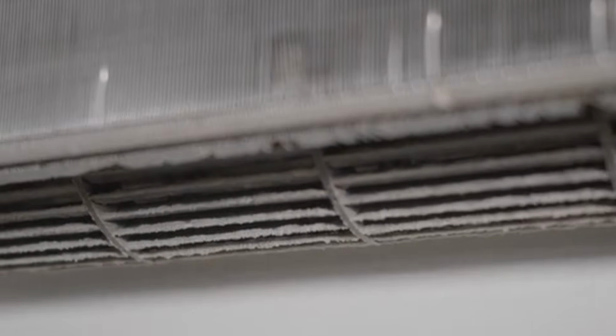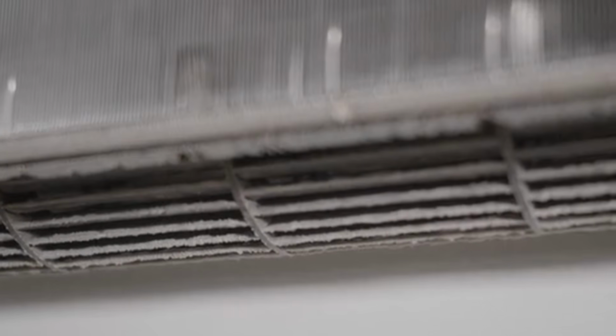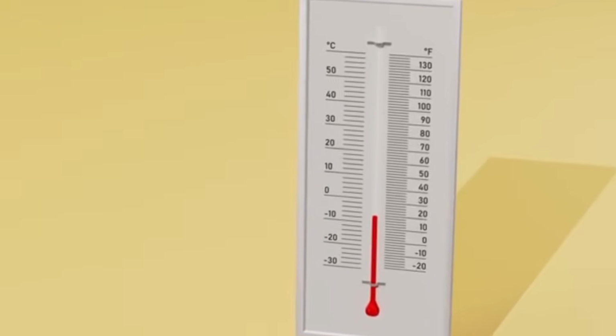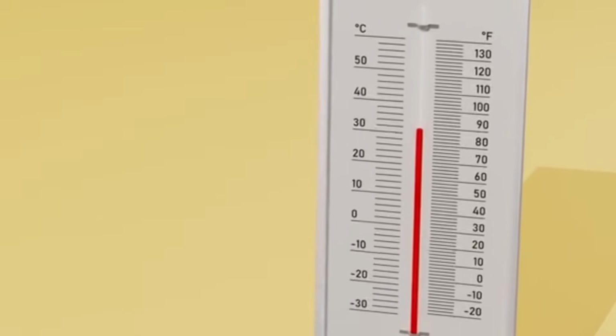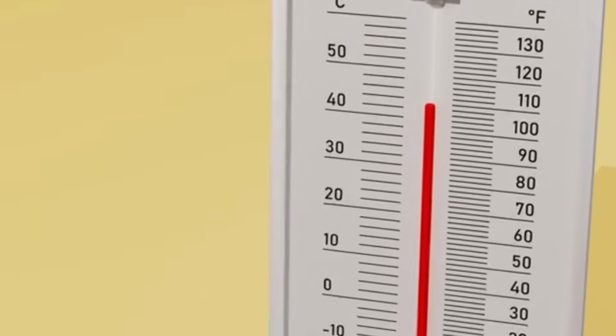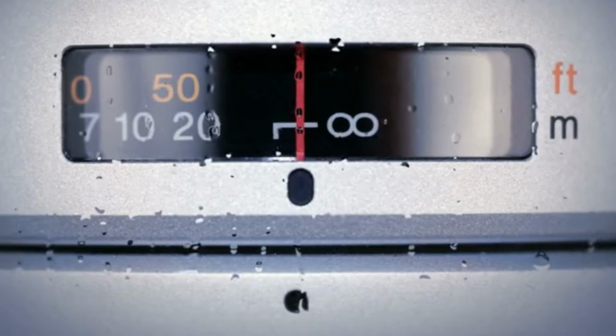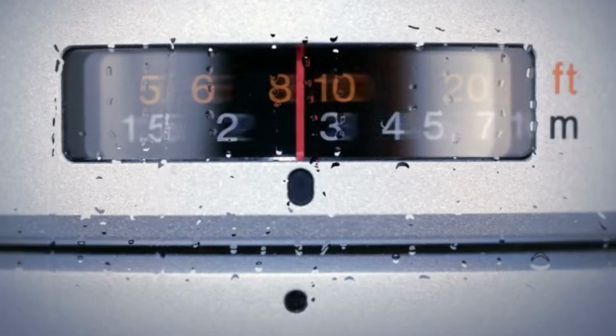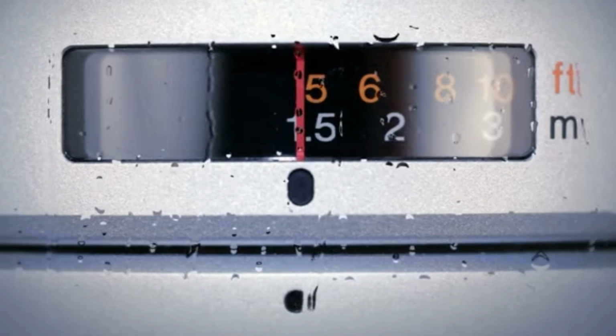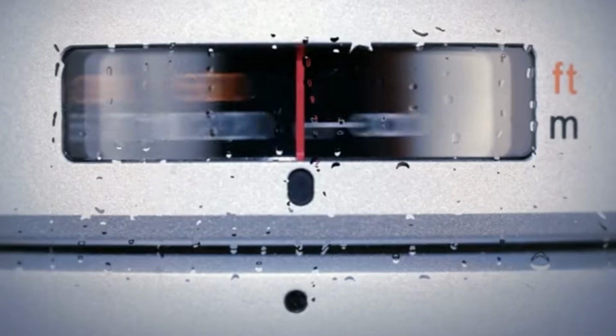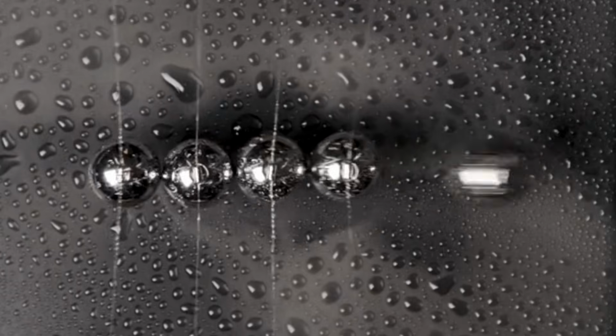However, and this is the part that most people miss, the radiator core, where the cold water meets the indoor air, will absolutely produce condensation just like an AC coil, as long as the radiator surface temperature is below the dew point of the indoor air. In most of the eastern and midwestern United States in summer, the dew point sits between 60 and 70 degrees. Your radiator fed by 54 degree water sits at about 58 degrees. That's below the dew point. You will get condensation, you will get dehumidification.